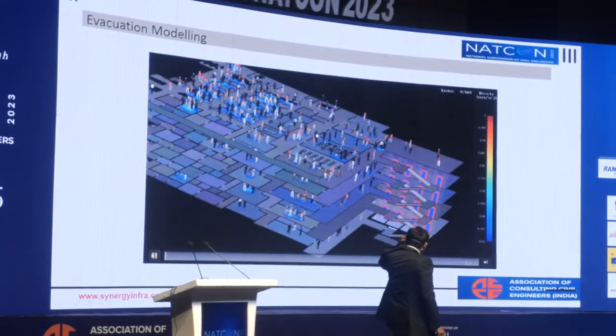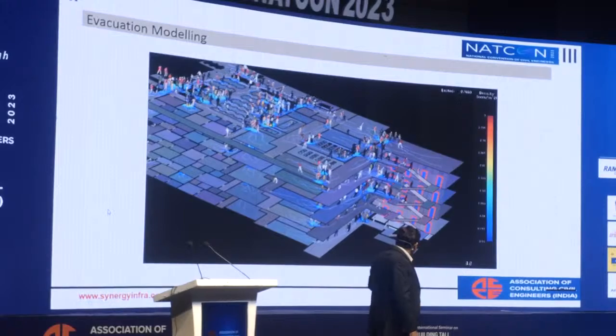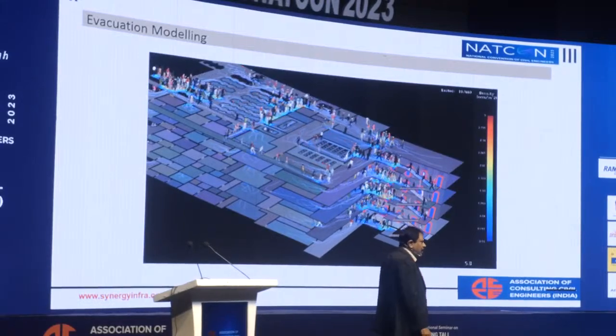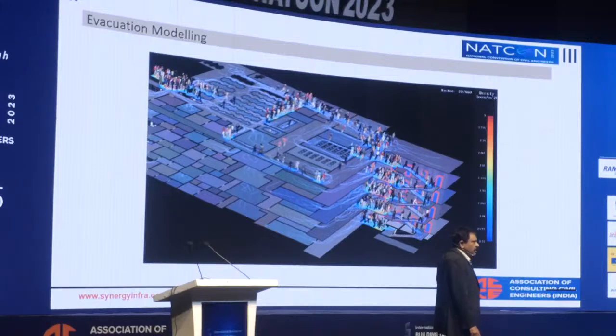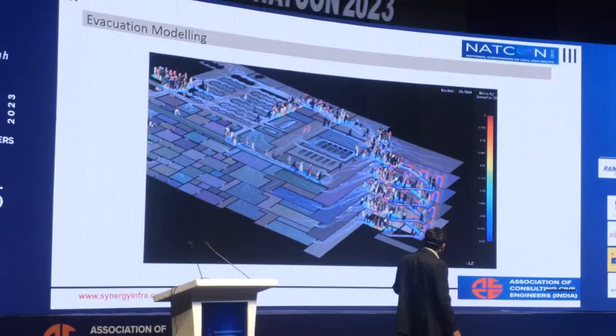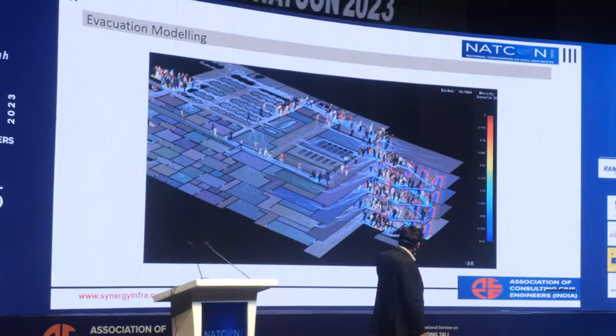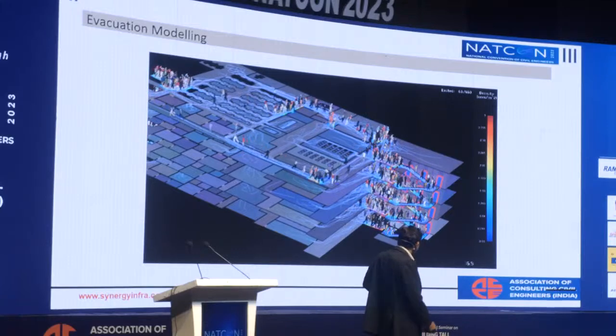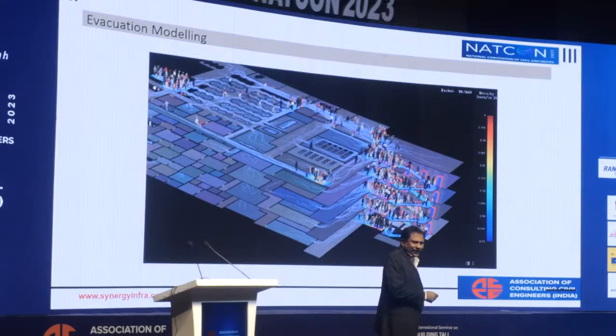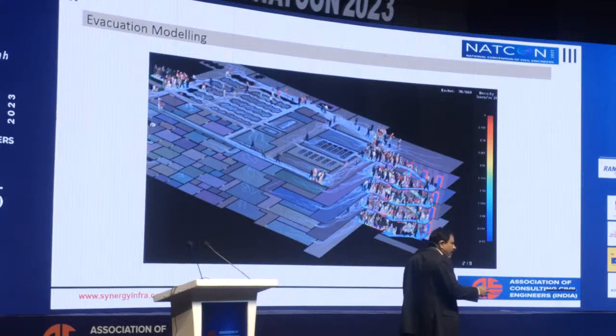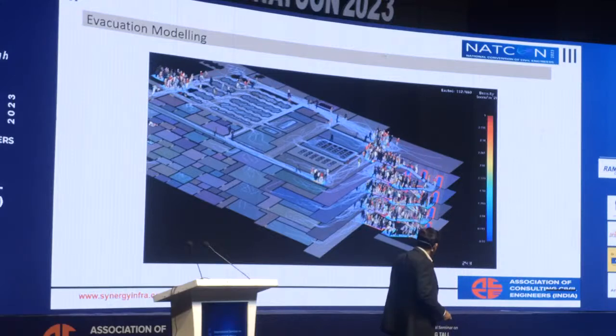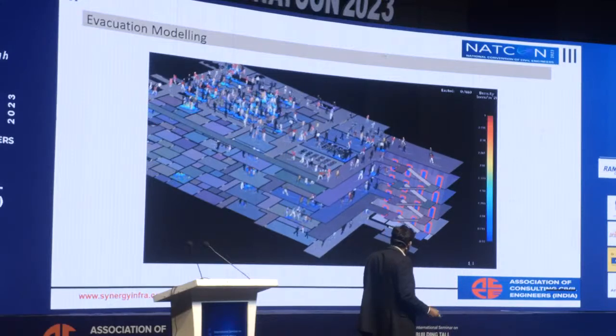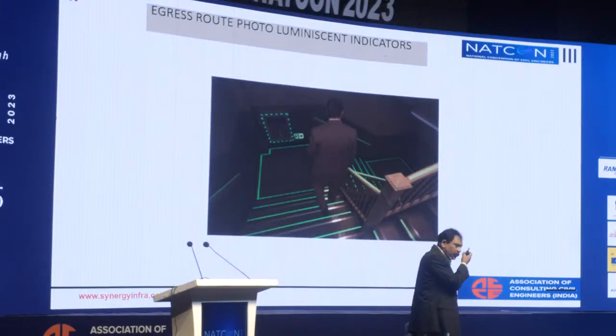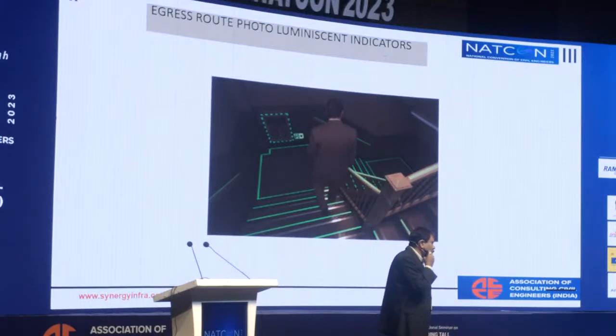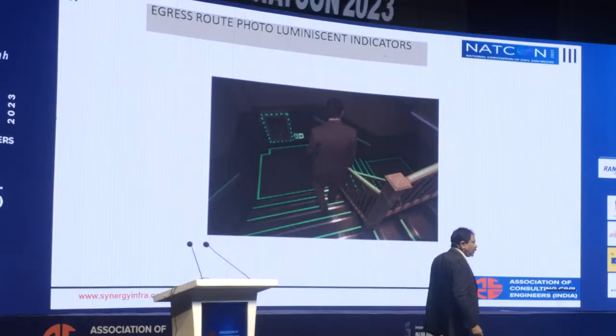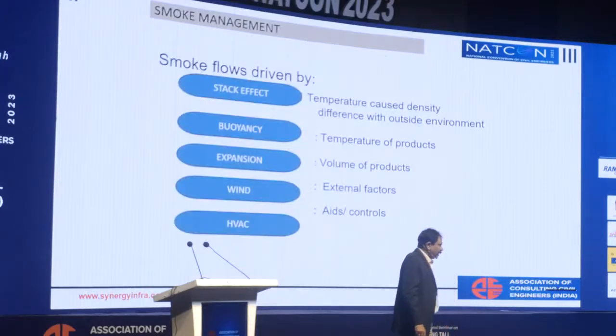So you can do this kind of analysis and find out, right from the beginning to the end, once the alarm is initiated, how much time the people need to be evacuated to a safe place. That is one thing. And each staircase, this was also done by us for that particular case to convince them, is within around 25 minutes, so there may not be any major issue. And we created, of course, additional staircases. Otherwise, it cannot be met. And then for the egress routes, it is suggested as per the new codes to have photoluminescent indicators, not depend totally on emergency lighting and other things.